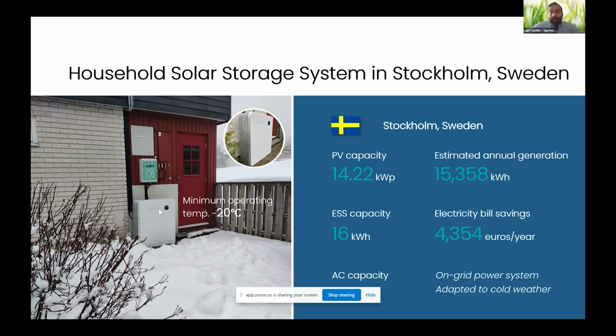So what we have done to overcome this challenge is we have added heating pads at the battery pack level. Every battery pack has its own dedicated heating pad that will regulate the temperature and increase the temperature in the event of the cell temperature dropping down to 0. This is with the idea to keep a charge and a discharge rate during cold temperatures. The charge and discharge rate of a battery cell, of the LFP cells at least, are a function of the state of charge and the cell temperature. So it's not a linear relationship. So what we aim to do is to keep the cell at a temperature where it's still able to charge and discharge.